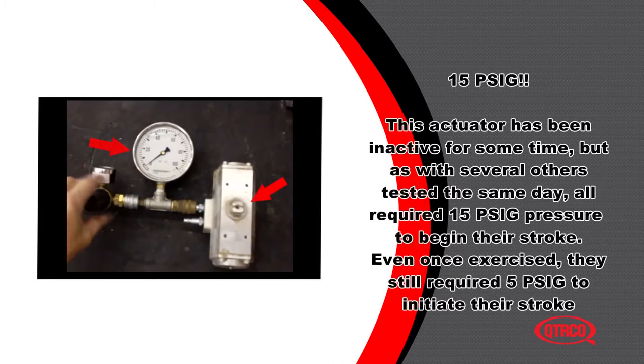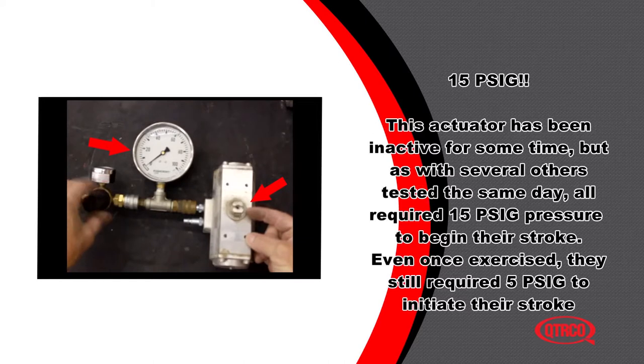How much pressure is required to stroke our competitor's actuator? 15 PSIG. This actuator has been inactive for some time, but as with several others tested the same day, all required 15 PSIG pressure to begin their stroke. Even once exercised, they still require 5 PSIG to initiate their stroke.